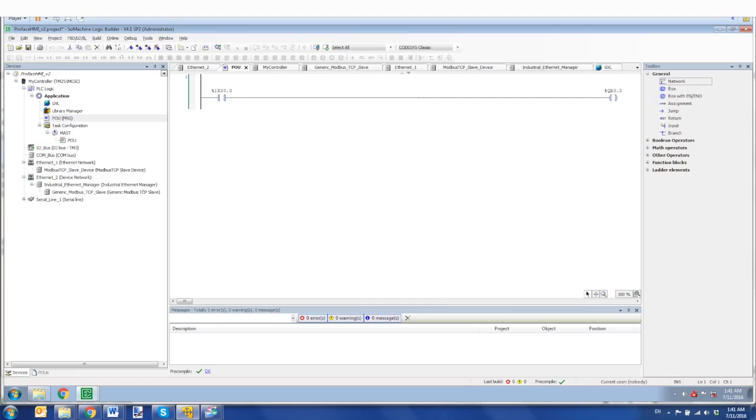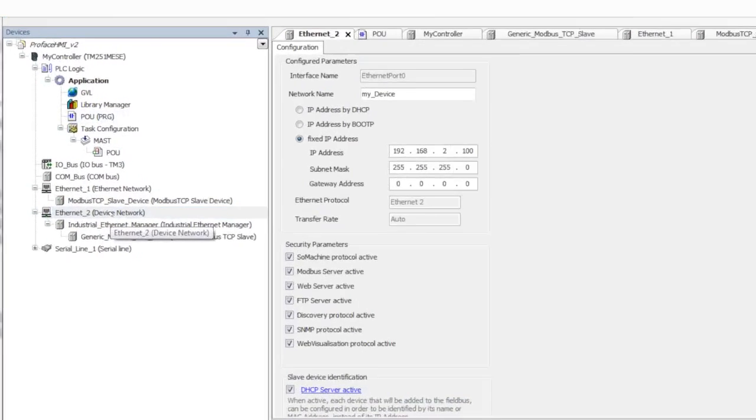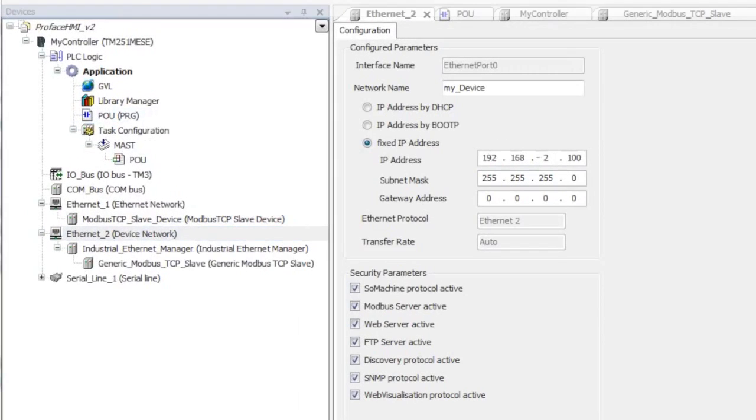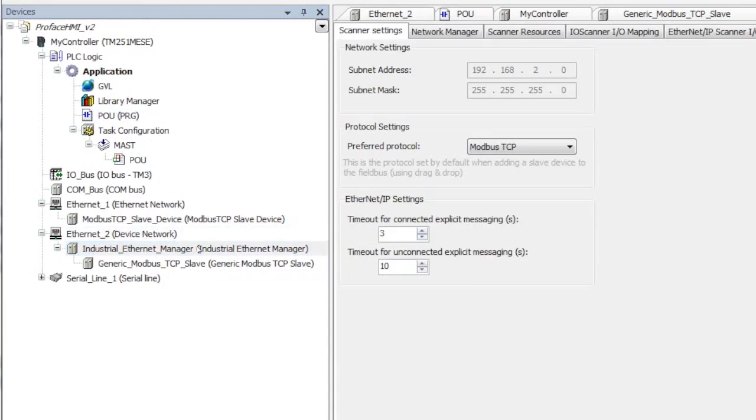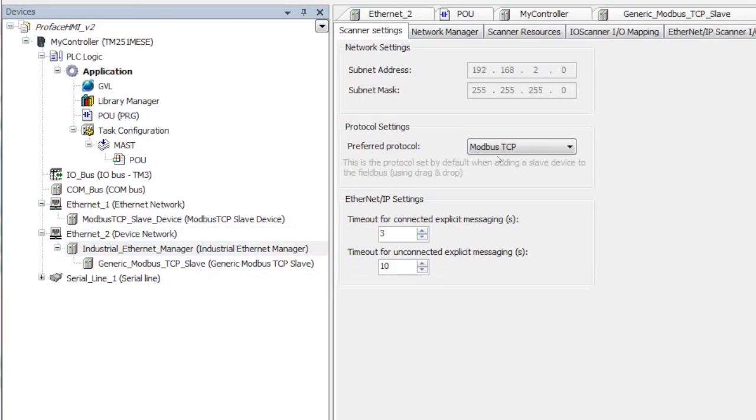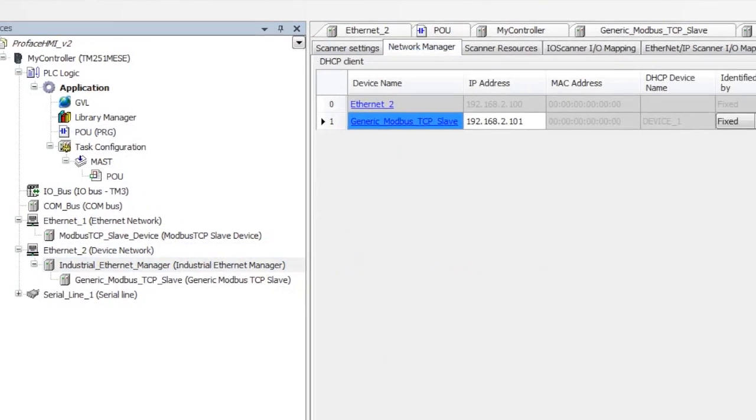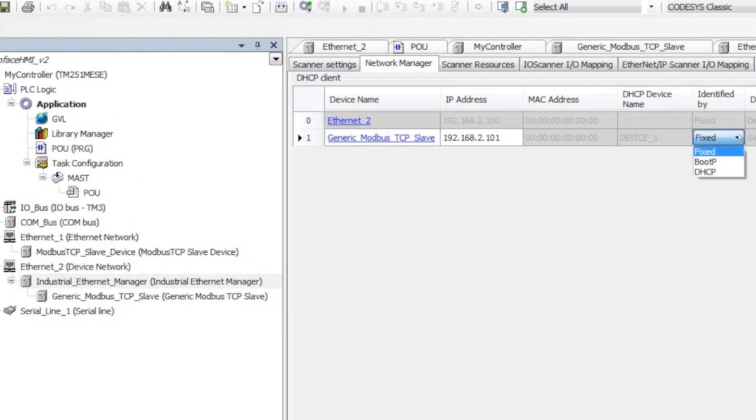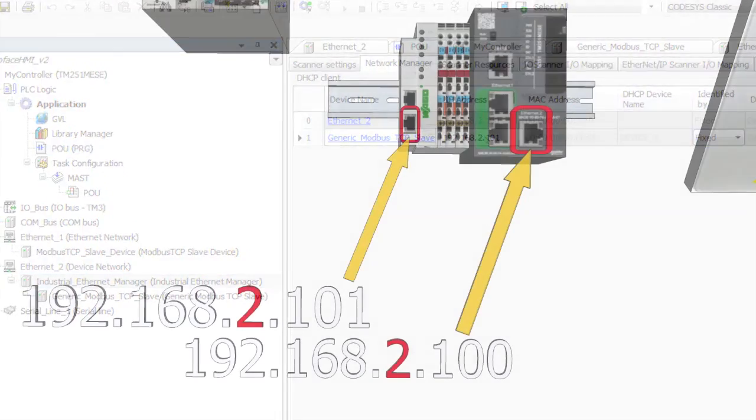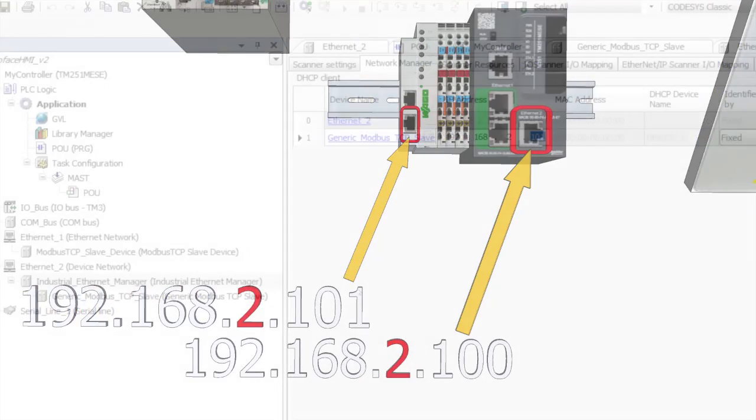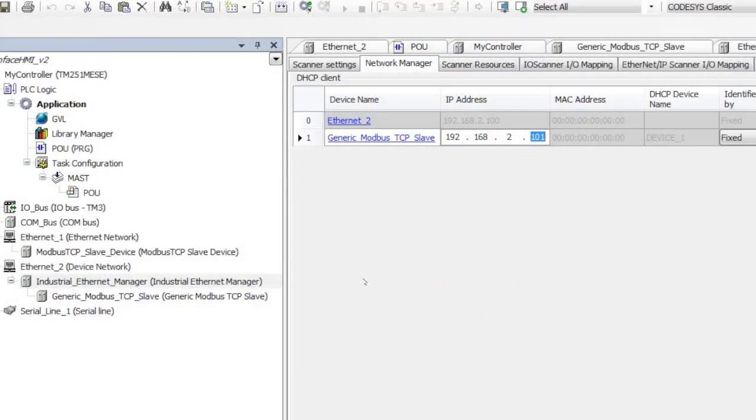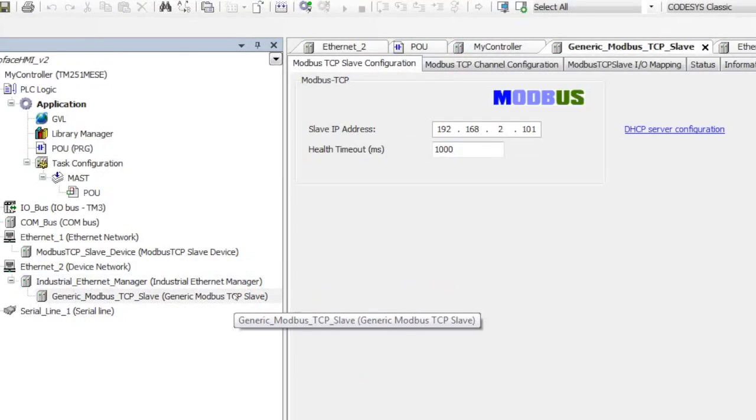Now for the Modbus I/O scanner on Ethernet 2, I have an IP address of 2.100. And in addition to that, I've added the I/O scanner. And in order to do that, I right clicked, I added an industrial Ethernet manager, selected Modbus TCP. Then for the network manager, I set it as fixed. And I'm pointing to the fixed IP address of the WAGO island. And on that, if I open up those settings here, you can see 2.101.